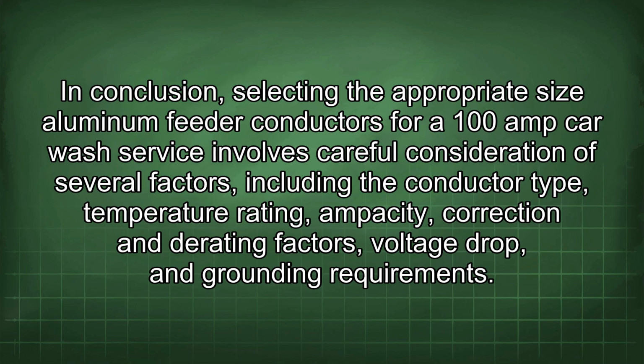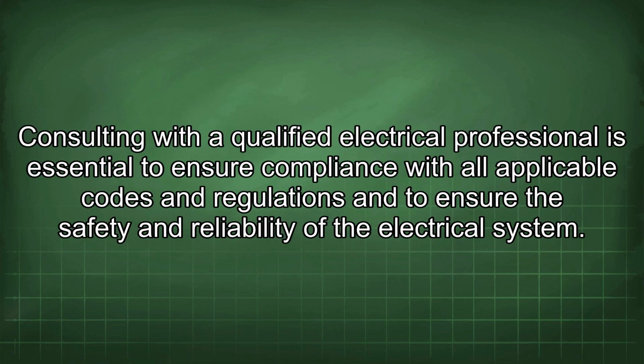In conclusion, selecting the appropriate size aluminum feeder conductors for a 100 amp car wash service involves careful consideration of several factors, including the conductor type, temperature rating, ampacity, correction and derating factors, voltage drop, and grounding requirements. Consulting with a qualified electrical professional is essential to ensure compliance with all applicable codes and regulations and to ensure the safety and reliability of the electrical system.